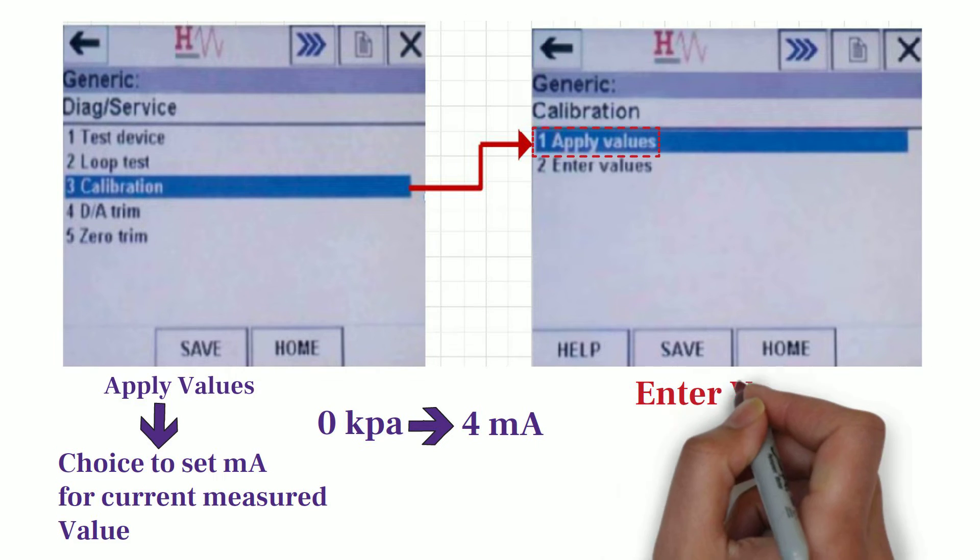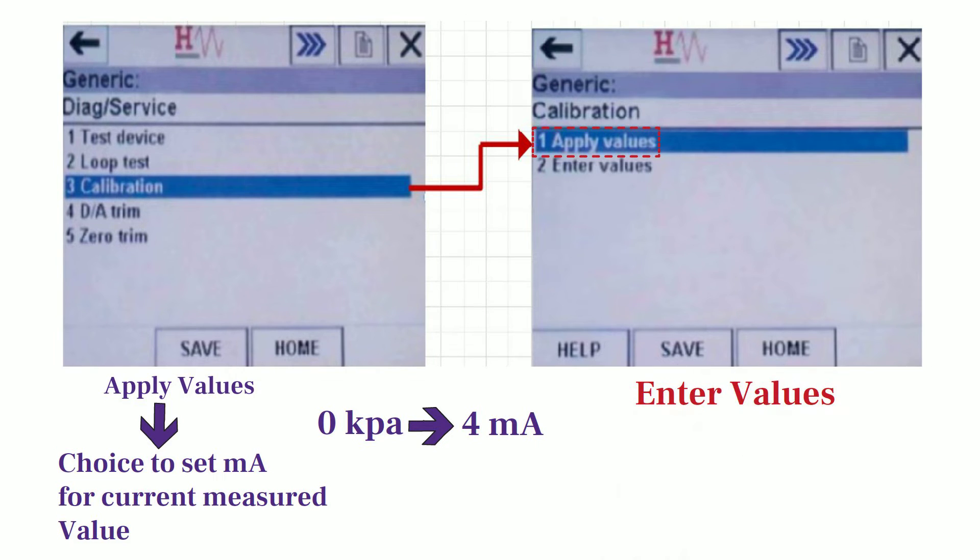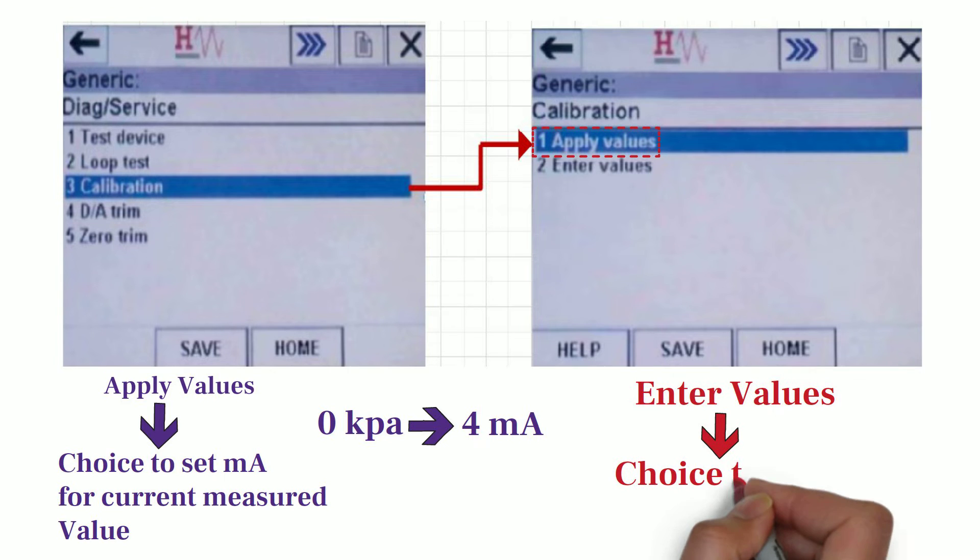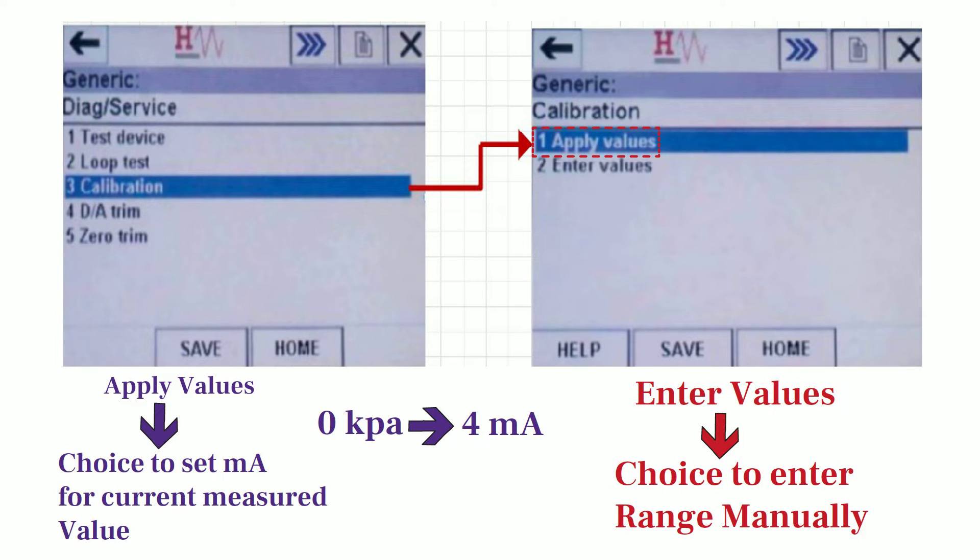The second option is Enter Values. This option gives you choice to enter the range manually. For example, if your pressure transmitter's range is 0 to 1000 kPa and you want to set 4 milliampere for 0 kPa and 20 milliampere for 1000 kPa, then you can do this thing by using this option.